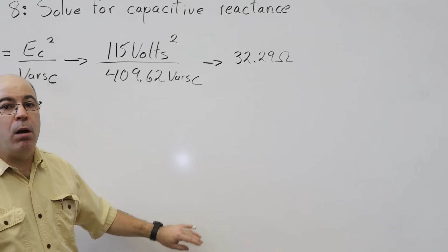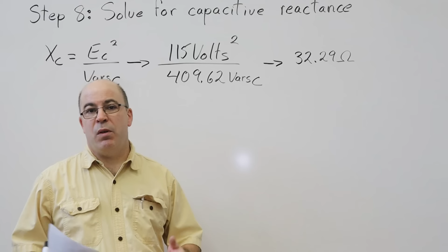We're going to take the 115 volts, which was the rating on the motor itself from our given values, and the VAR_C value we just calculated, 409.62 VARs sub C. Putting that into a calculator, you should get a capacitive reactance of 32.29 ohms. As always, we round to 2 decimal places, which is the standard in the program here at Cambrian College. So we got a capacitive reactance of 32.29 ohms.